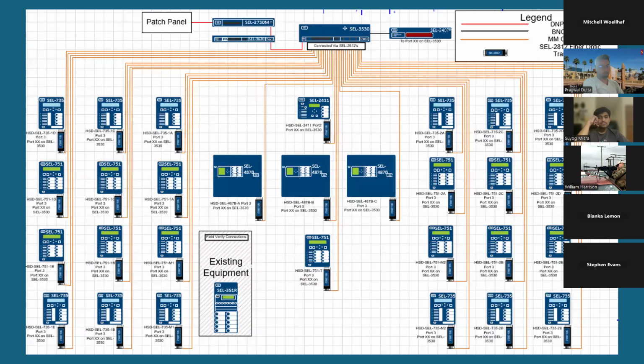Next slide, please. We're utilizing the SEL communication architecture network setup for our design. The slide shows an example of the networking system from the hardware that we're using. We're using SEL-3530 real-time automation controllers as central nodes. These interface with relays like the SEL-751 for feeder protection and the SEL-735 for power metering. Communications are handled over DNP Ethernet with coaxial and fiber cables. Each line type is mapped out in this diagram.